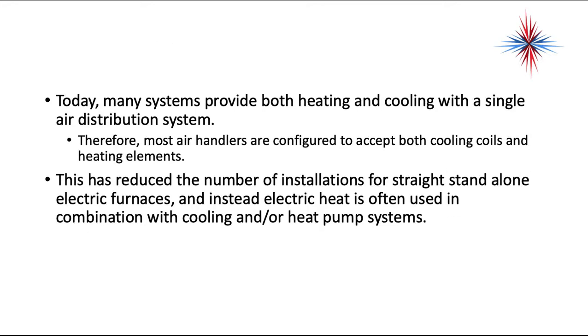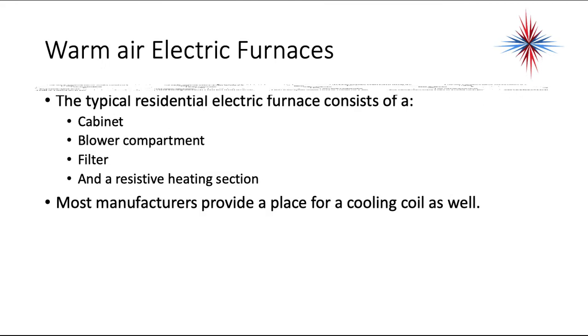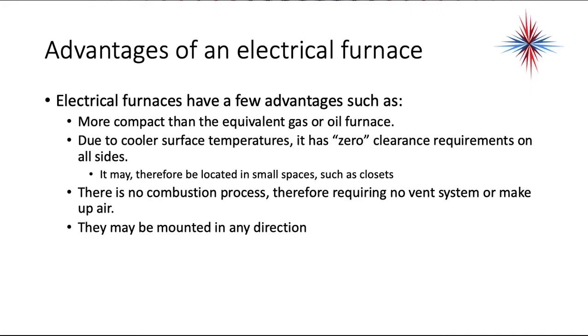Today, many systems provide both heating and cooling with a single air distribution system. Therefore, most air handlers are configured to accept both cooling coils and heating elements. This has reduced the number of installations for straight standalone electric furnaces, and instead electric heat is often used in combination with cooling or heat pump systems. A typical residential electric furnace consists of a cabinet, a blower compartment, a filter, and a resistive heating section. Most manufacturers, when manufacturing air handlers for electric heating, provide a cooling coil as well.